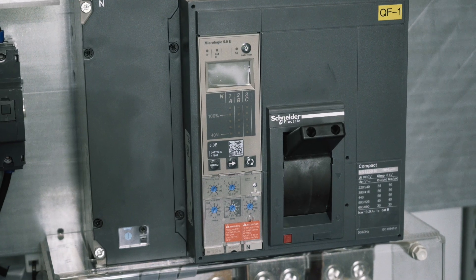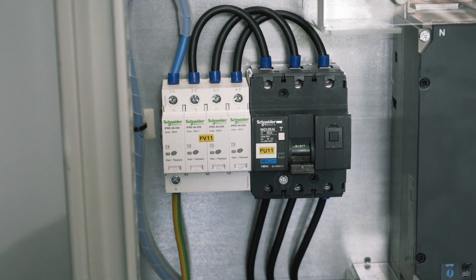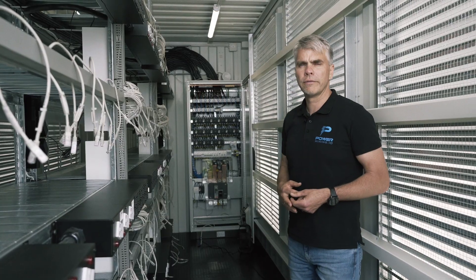The main electricity panel is four pole — four pole breakers for PDUs, and in this configuration a four pole 1600 amp automatic breaker at the electricity input. So our Norwegian friends, where renewable energy is booming, you are welcome.